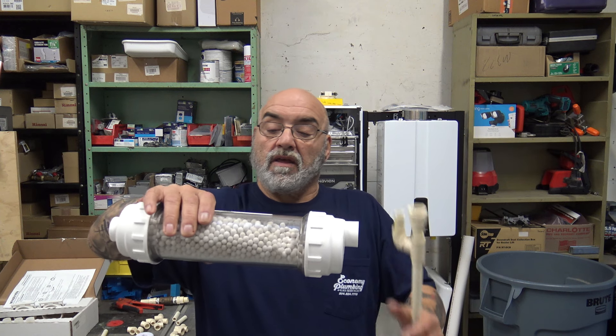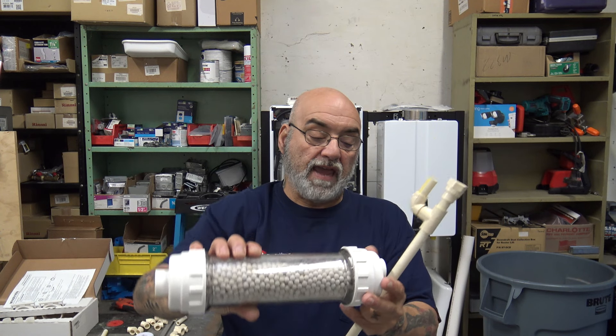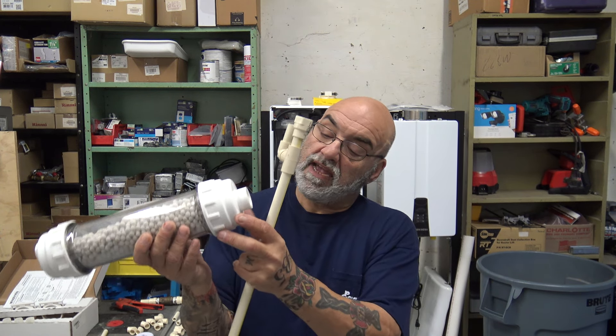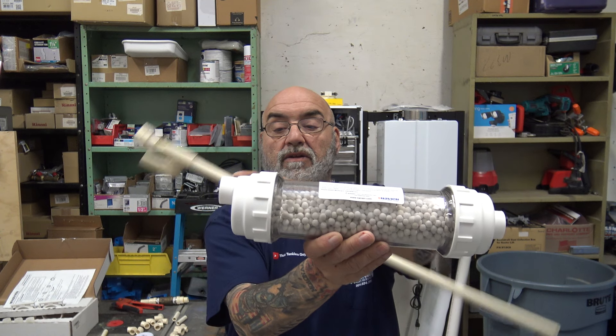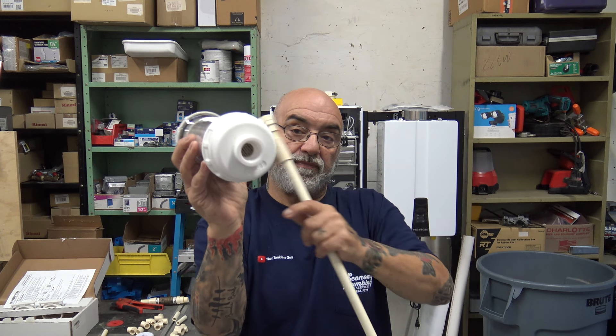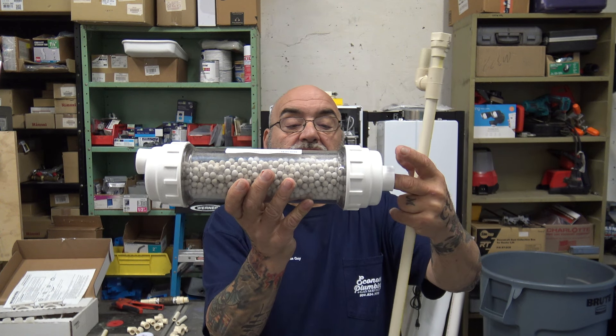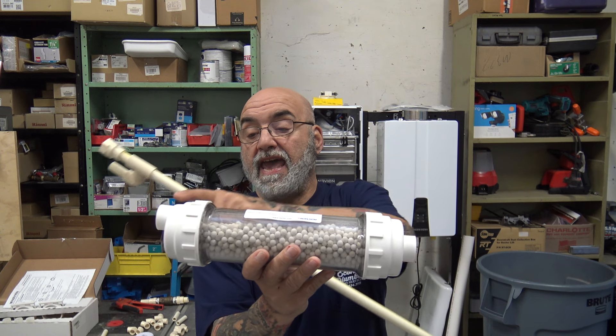This is Navien's neutralizer. I'll show you the instruction sheet. This is the neutralizer — it's filled with these pellets. This is the inlet right here, and the outlet is higher — notice it says outlet and inlet. The inlet goes in the middle. There would be a bypass; it comes with hoses. The condensate would go through here, get mixed with these pellets, get neutralized, exit, and go to the sewer.